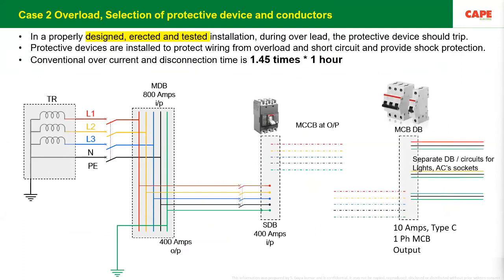overload. After every accident nowadays, we say the accident is due to overloading of the circuit. The building was designed 25 years back. Then we added an air conditioner, refrigerator, heater, and so on. As a result, the load has increased. Then the fire or the accident happened. Actually, electrical engineers shall not make this claim, because an electrical engineer knows that there are protective measures implemented in a certain installation, and the protective devices are supposed to operate before the electrical installation causes a serious accident.